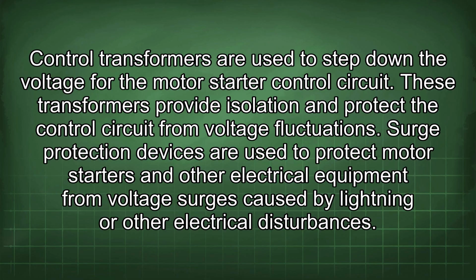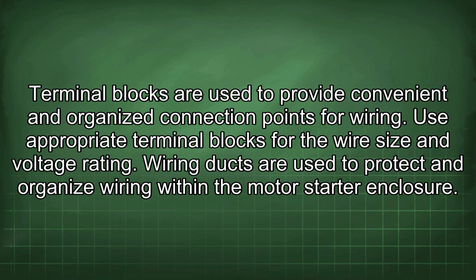Control transformers are used to step down the voltage for the motor starter control circuit. These transformers provide isolation and protect the control circuit from voltage fluctuations. Surge protection devices are used to protect motor starters and other electrical equipment from voltage surges caused by lightning or other electrical disturbances. Terminal blocks are used to provide convenient and organized connection points for wiring. Use appropriate terminal blocks for the wire size and voltage rating.